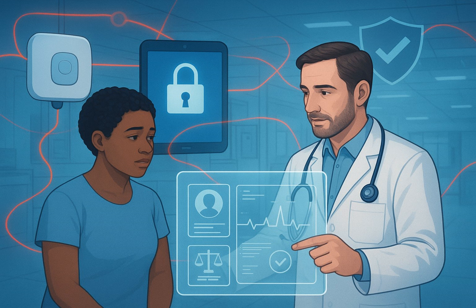You just can't effectively bolt on security later to systems that were never meant to be connected or secured in the first place. And it seems the FDA has really been stepping up its efforts here. They had guidance back in 2005, sure, but this recent report, I think it was June 2025, specifically calls for secure by design products. That feels like a big change. It's a significant evolution, definitely, and it raises that key question. What does secure by design actually mean for the manufacturers? Well, the FDA, under this new authority from the Food and Drug Omnibus Reform Act, FDORA, which kicked in March 2023, now has a formal definition for a cyber device. And for these devices, there are much stricter pre-market submission requirements.